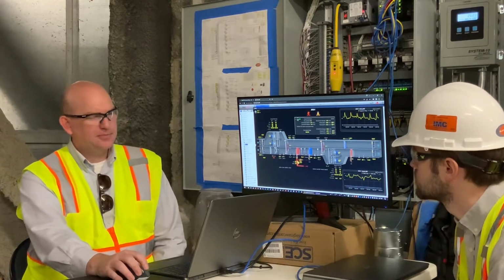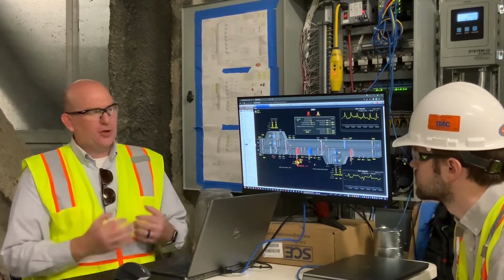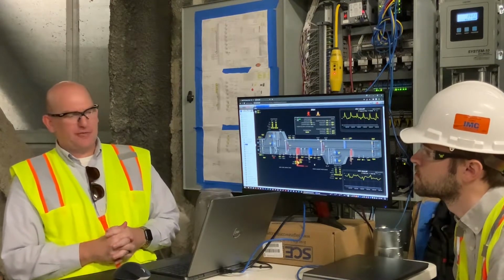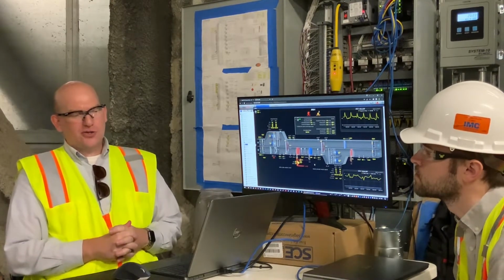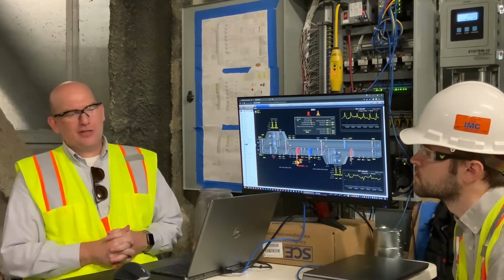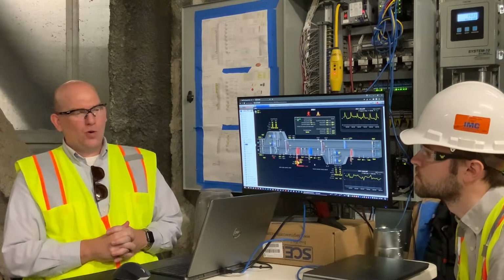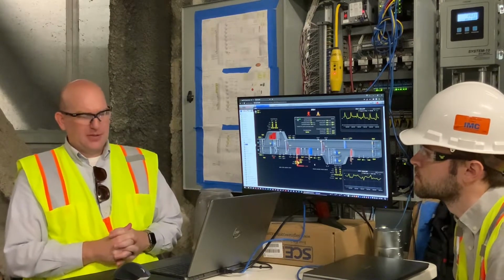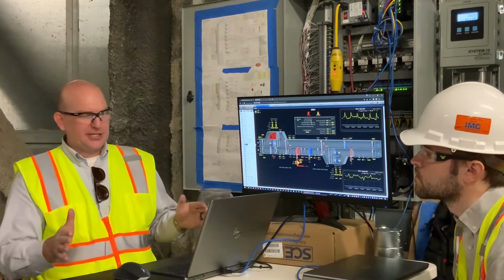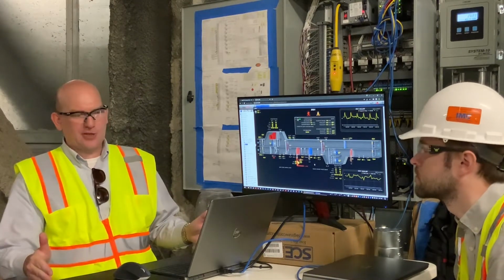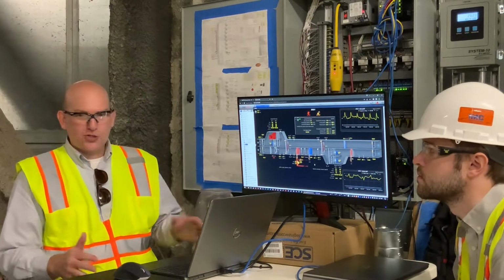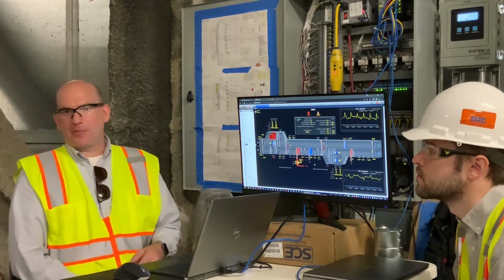So right now, the building as constructed has 4 air handlers on the main delivery system. They all service a common plenum for both the supply and the exhaust. What that means is if one of the air handlers goes down, we have to make sure that isolation dampers on the OA and the supply and the exhaust and the return all close, because we can lose air from the plenum through it.